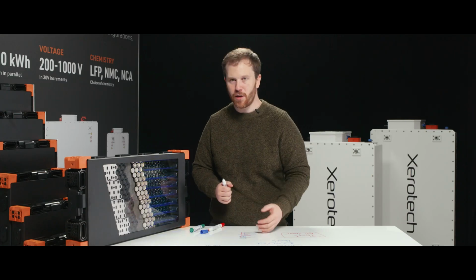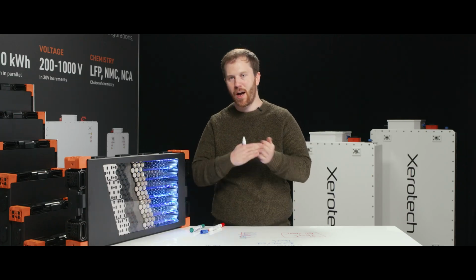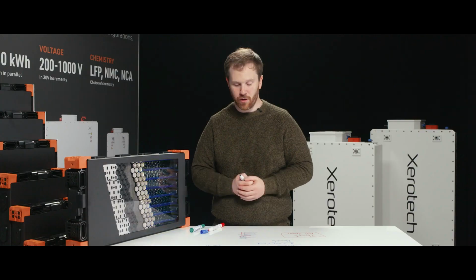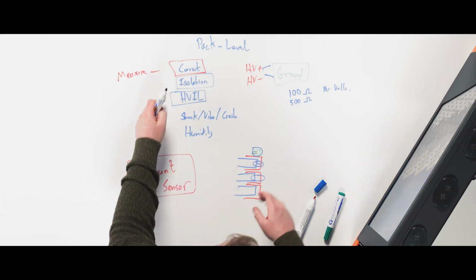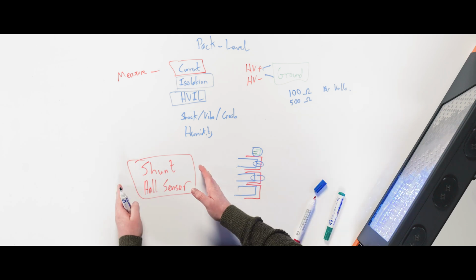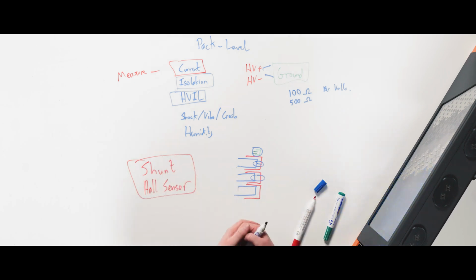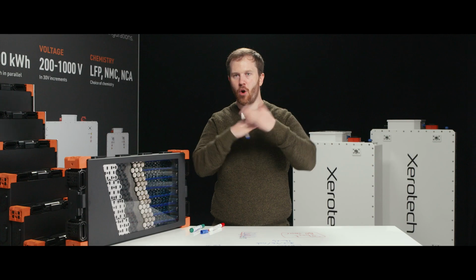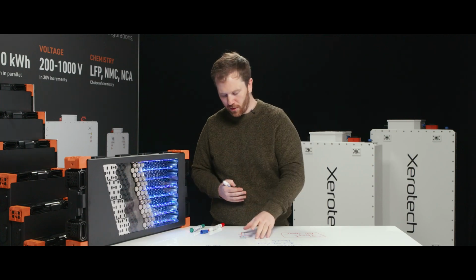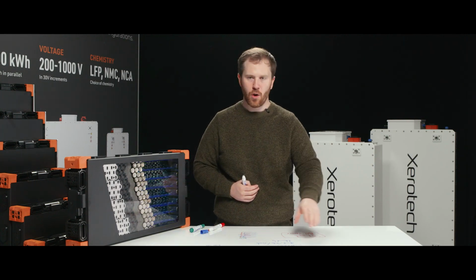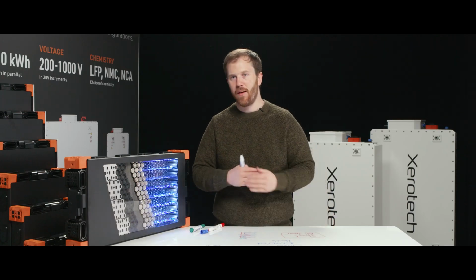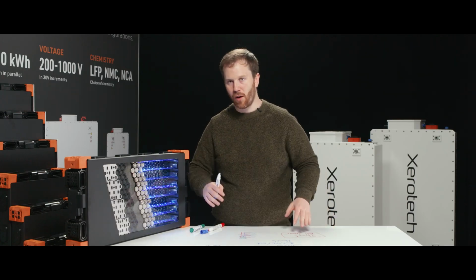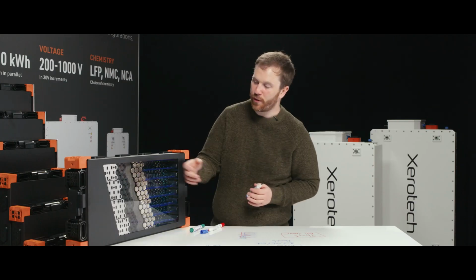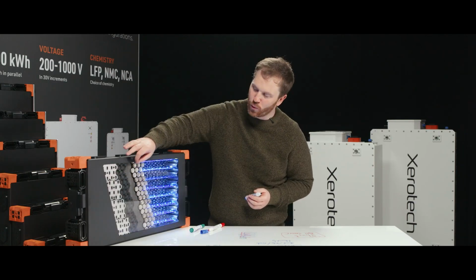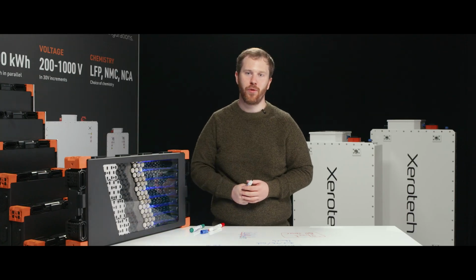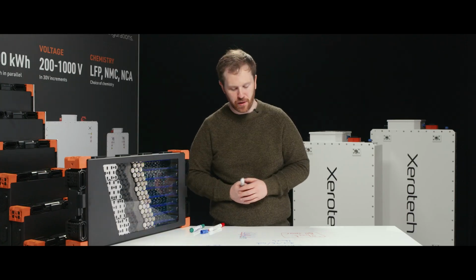Hopefully they'll do that, and if they don't, within a few tens of milliseconds, the contactors are going to open, potentially under load. And in relation to current and short circuits and other factors, we do also have further levels of protection with fuses. So we have active protection, that we can open the contactors under load, but that does cause a lot of damage to the contactors. We have mechanical fuses in some cases that will burn and blow and break the circuit. But in a Xerotech module, we also use cell level fuses. Every cell is wire bonded, which acts as an electrical fuse as well, a further third level of safety.